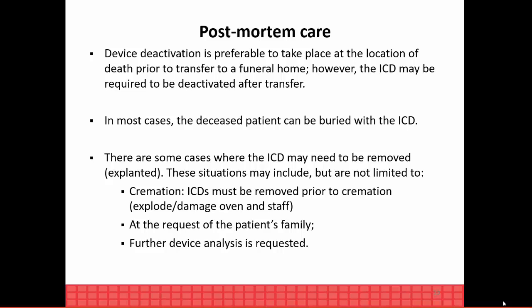If they are cremated, the device must be removed. This is an explosion hazard and can cause damage to the crematorium as well as the staff. It's advised that devices are returned to the manufacturer for analysis.